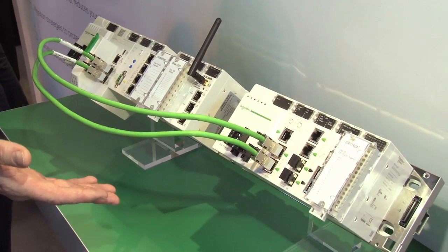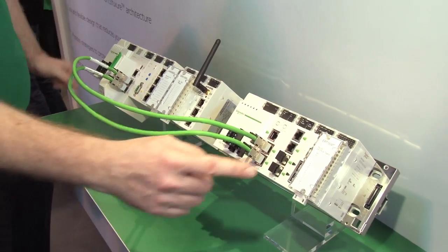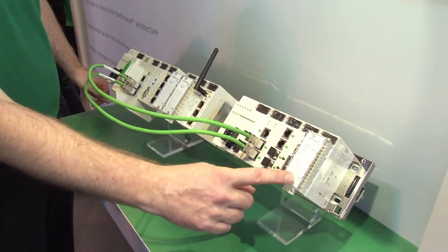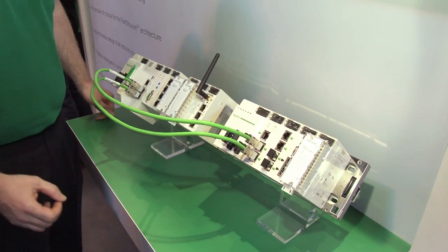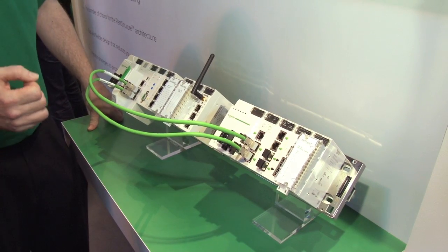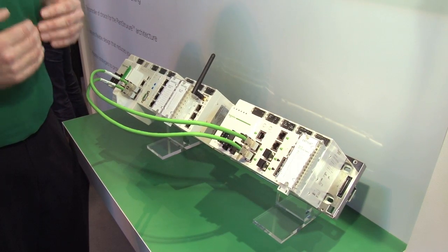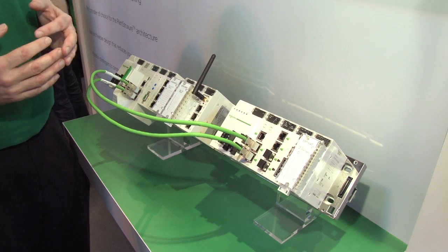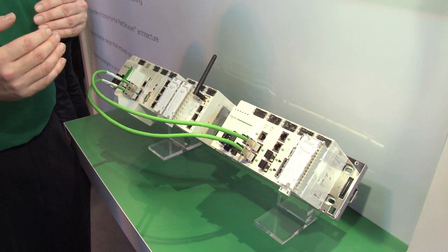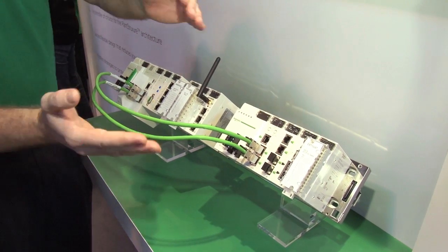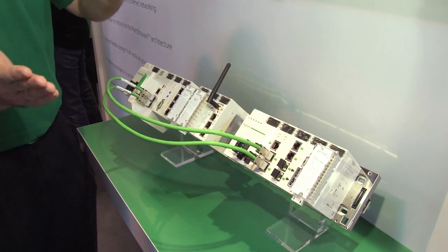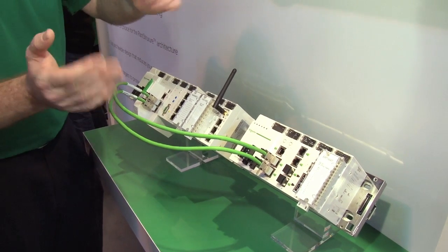Other elements of the M580 are on show here. We have this dedicated module here, the ERT module. That's capable of timestamping. So in terms of capturing sequence of events data to track and trace the root cause of a failure, this module can timestamp and hold all that data on board down to a resolution of 10 milliseconds.